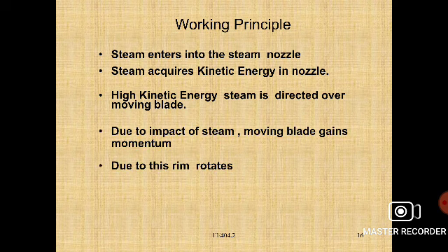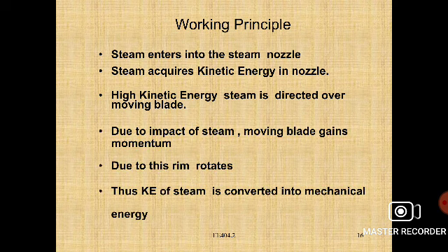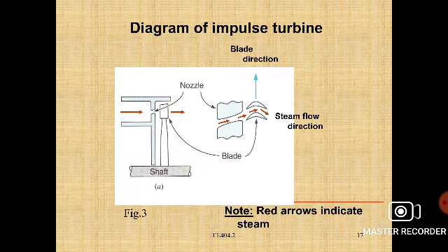Then next, what is the working principle? The steam enters into the steam nozzle. Steam acquires kinetic energy in the nozzle only. The high kinetic energy steam is directed over the moving blades. Due to the impact of the steam, the moving blades gain motion. Thus the kinetic energy of the steam is converted into mechanical energy.